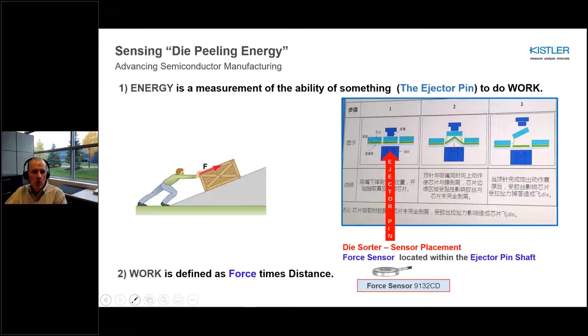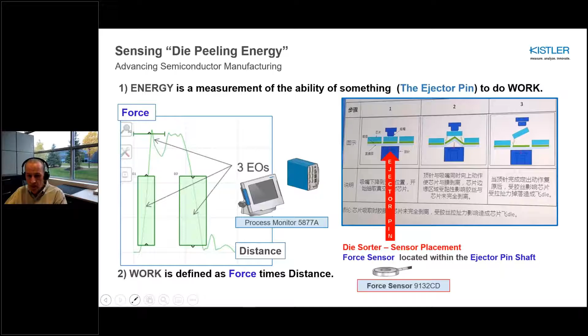On the left side, we view a curve that has the pin position or distance plotted on the lower x-axis, and the pin force, which is the effort encountered on the pin during its movement, plotted on the y-axis. The work performed in removing the chip from the membrane is the integral of this curve, or more simply stated as the area under the curve. The process monitors utilized to track both these parameters provide a detailed signature of the process. A pass-fail toolbox within these monitors provides for waveform evaluation as well as reporting for traceability that is tied to each die removal.